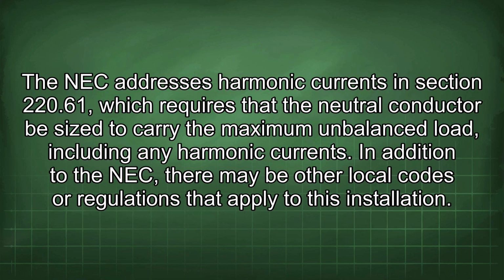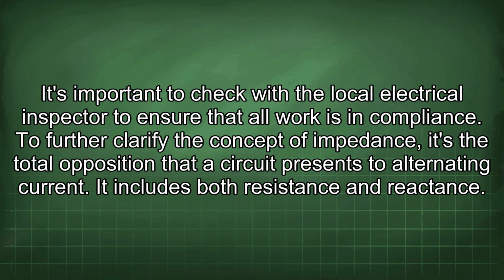The NEC addresses harmonic currents in section 220.61, which requires that the neutral conductor be sized to carry the maximum unbalanced load, including any harmonic currents. In addition to the NEC, there may be other local codes or regulations that apply to this installation. It's important to check with the local electrical inspector to ensure that all work is in compliance.